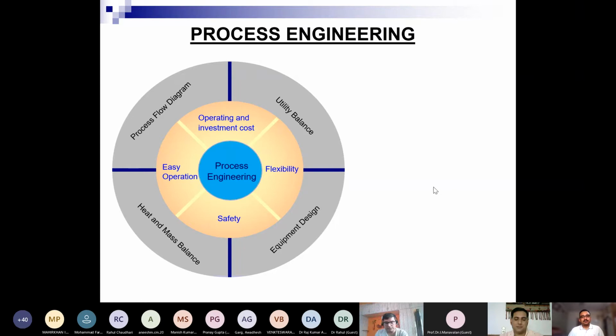But if the customer wants to run the unit for less than the turndown flow, like 30-40%, we analyze this because some instruments like control valves will not operate well there. There may be a bypass control valve, or a different control valve has to be designed for that lower turndown flow, because the rangeability of the control valve designed for 100% or 50% turndown flow may not work.